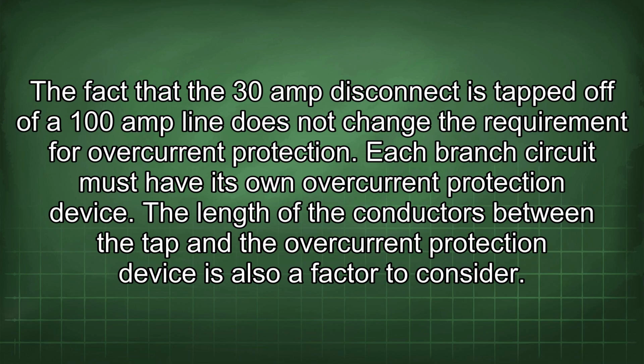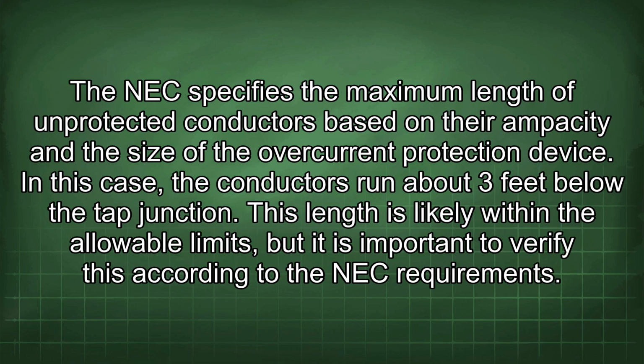The length of the conductors between the tap and the overcurrent protection device is also a factor to consider. The NEC specifies the maximum length of unprotected conductors based on their ampacity and the size of the overcurrent protection device. In this case, the conductors run about 3 feet below the tap junction. This length is likely within the allowable limits, but it is important to verify this according to the NEC requirements.